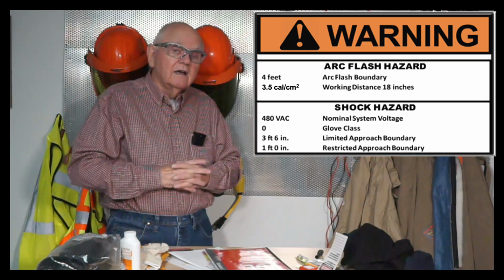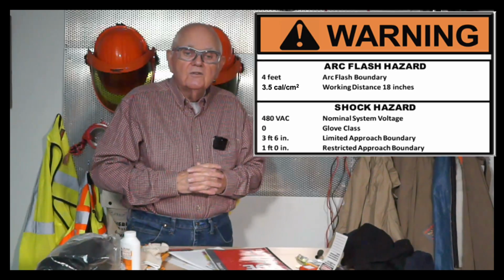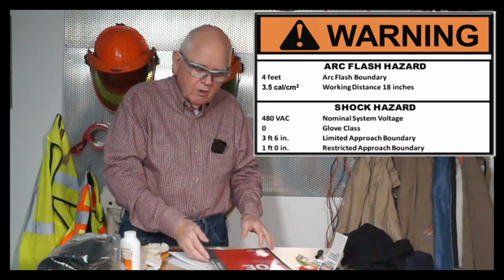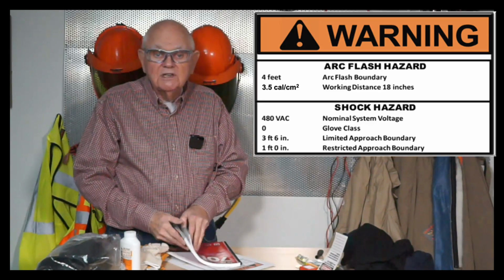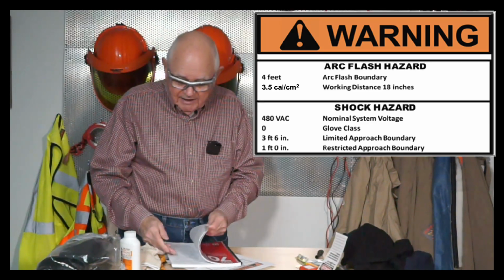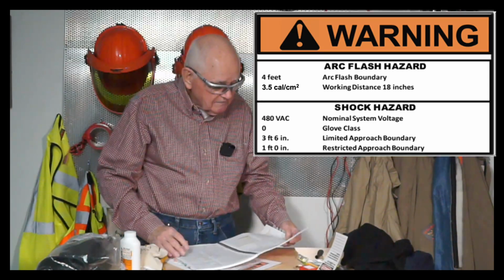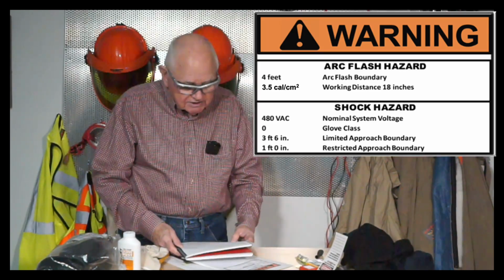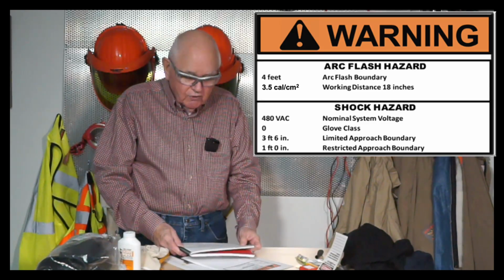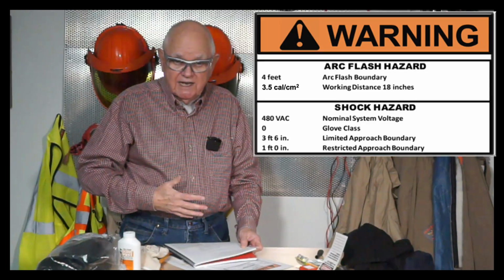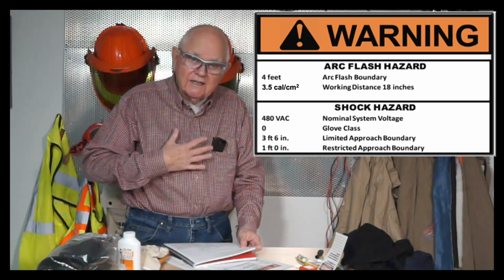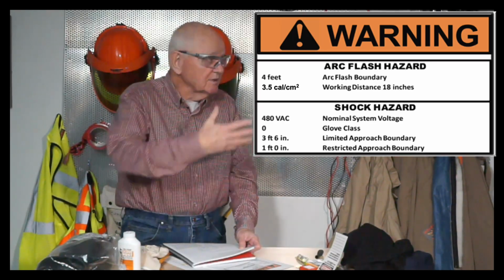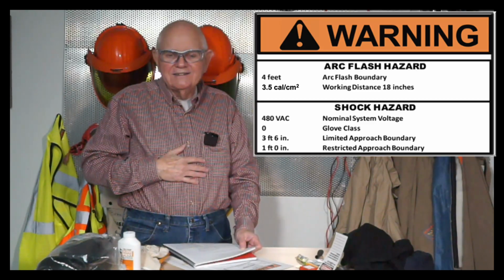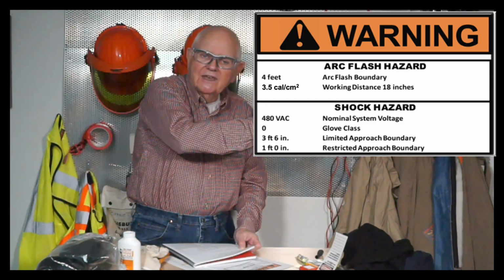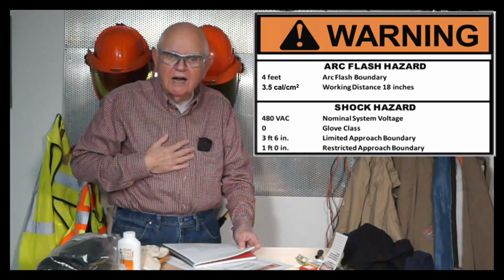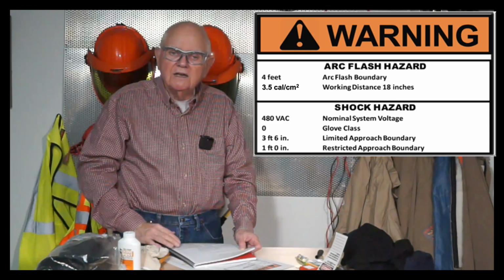Let's take an example right here. At 3.5 calories, if I were going to dress out for 3.5 calories, I would go to Table 130.5(G) or whatever the appropriate table is that you're using in your particular procedure, and I would take a look at 130.5(G), and it tells me for incident energy exposures equal to 1.2 calories up to and including 12 calories, it tells me how to dress out. Bottom line is the rating of my clothing has to be at least what the rating is for the incident energy on the label, right? Wouldn't make sense to face a 3.5 calorie arc and wear 1 calorie or just a cotton shirt or something like that. It would ignite, catch on fire. I could get 3rd-degree burns.